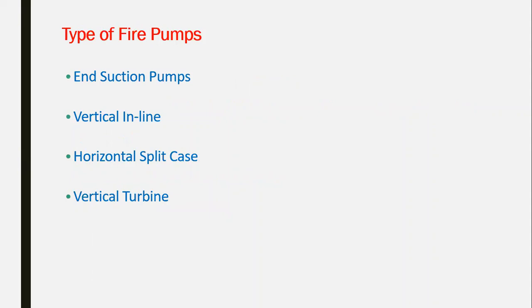The types of the fire pumps, which we talked about last time, just to remind me, we have four types. Horizontal split case is the commonly used, the famous one, applicable for buildings, either residential or industrial. It is commonly used because it covers a wide range of pump sizes and it is easy for maintenance. Most technicians and suppliers are familiar with the horizontal, and it can go for high pressure, so it serves high-rise buildings, and it can go for a huge discharge, up to 1000 GPM. The disadvantage of the horizontal split case is that it is installed horizontally, so it requires a big space for the firefighting pump. So this is a disadvantage of the split case unit.